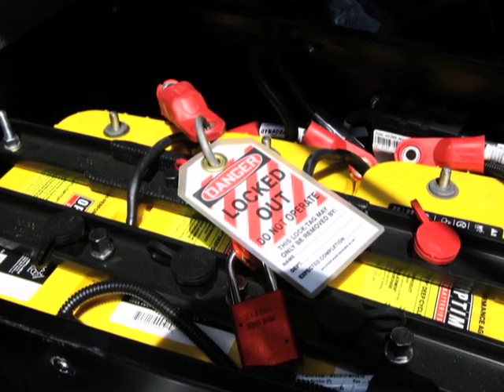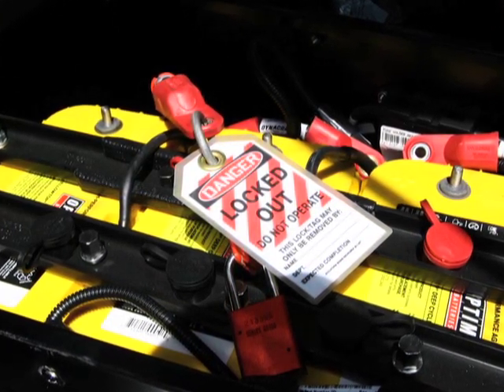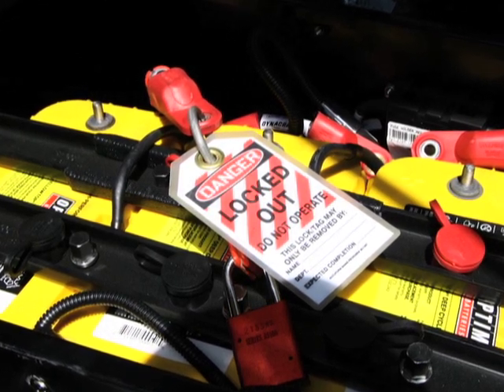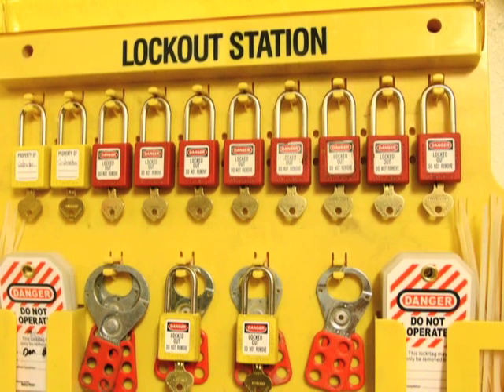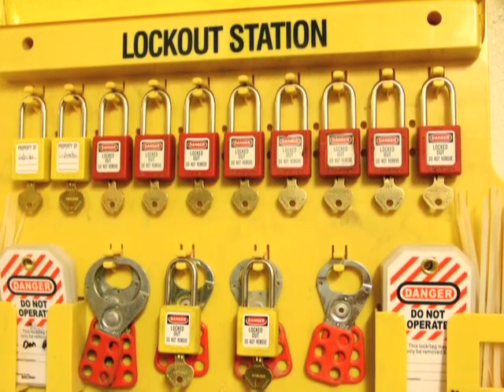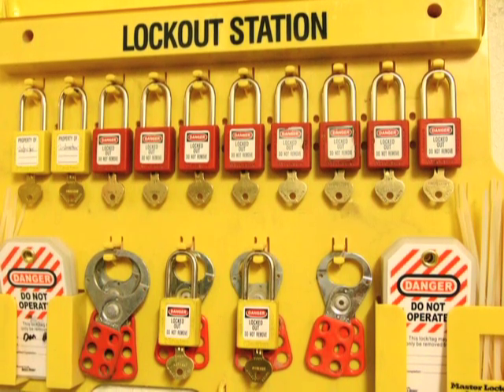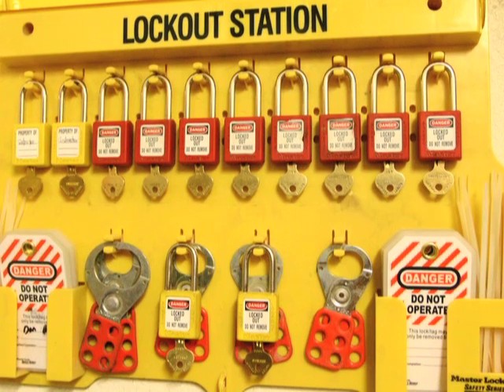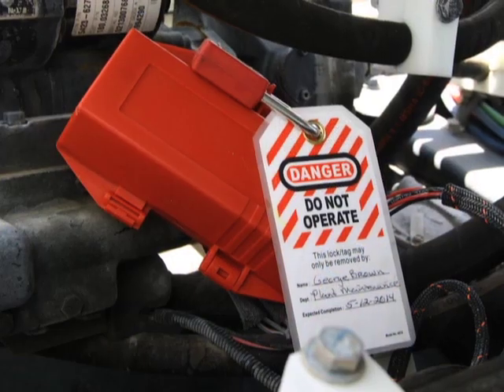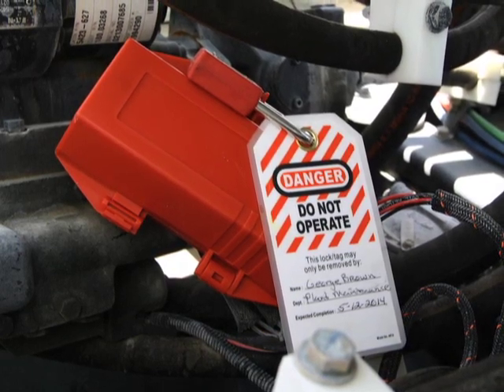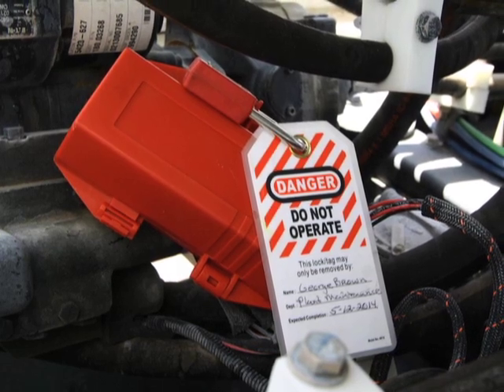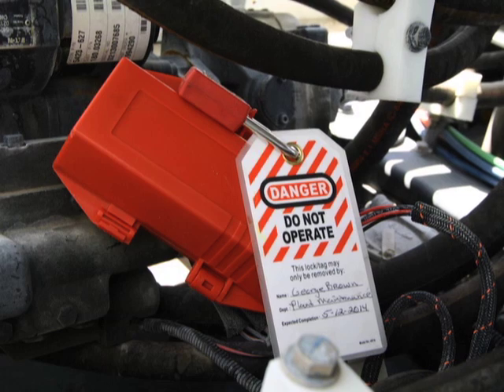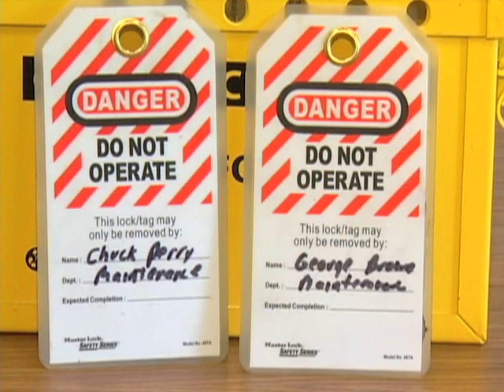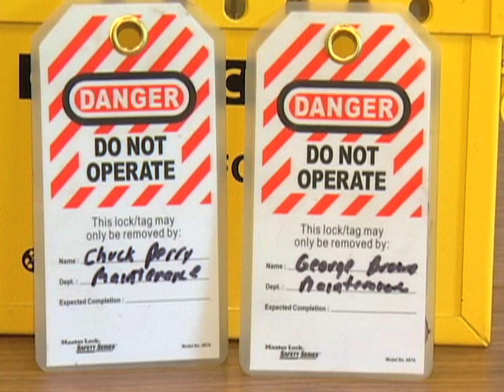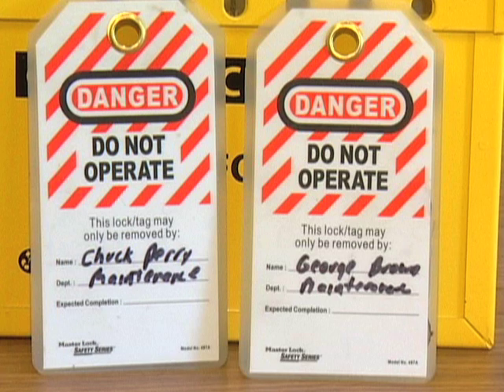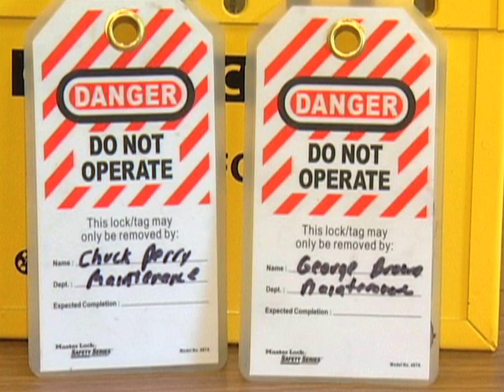Durable. The lockout tagout devices must be capable of withstanding the environment to which they are exposed for the maximum period of time the exposure is expected. Standardized. The devices shall be standardized within the facility in at least one of the following categories: color, shape, or size. Also, all tags must have the same print and format. Substantial. The device shall be substantial enough to prevent removal without the use of excessive force or unusual techniques, such as the use of bolt cutters or other metal cutting tools. Identifiable. The device shall clearly indicate the identity of the employee applying the device. All of these requirements must be met by devices in order to comply with the OSHA Lockout Tagout standard.